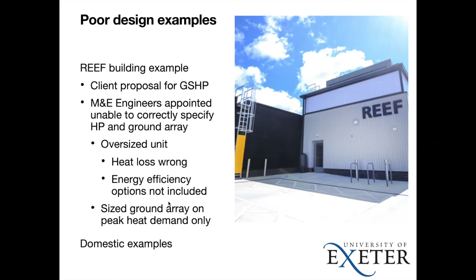Another example, what should have been a simple domestic installation. A company came in and the client wanted to know about heat pumps, air source or ground source. The contractor recommended an air source heat pump, done on simple calculations without considering things like energy efficiency. With the air source, there were no single phase units capable of providing enough heat, so they would have to upgrade to a 3-phase supply. That just made the whole thing unviable, too expensive to go ahead.